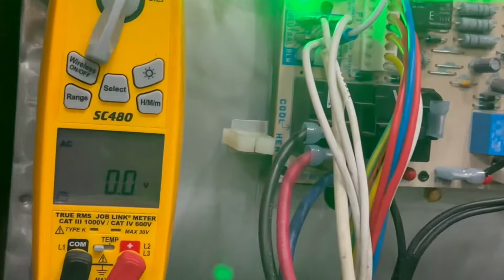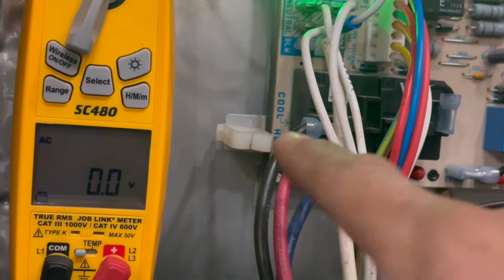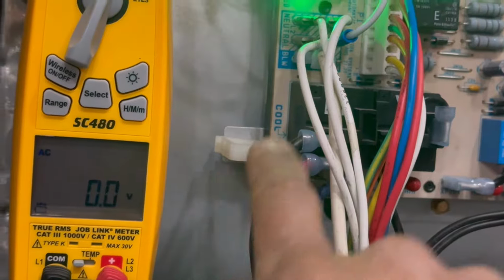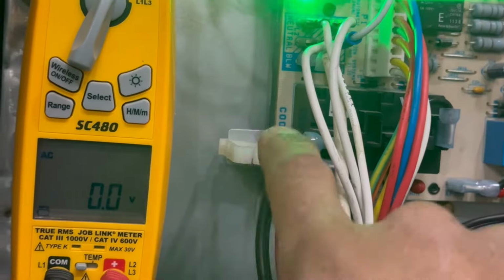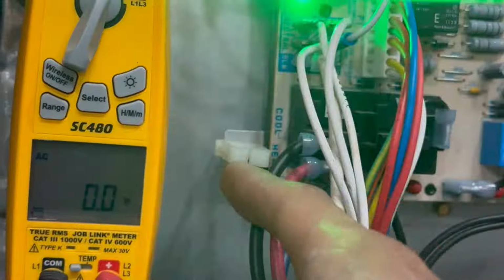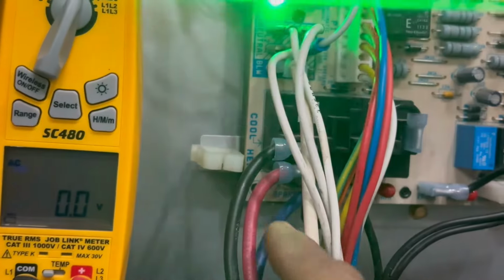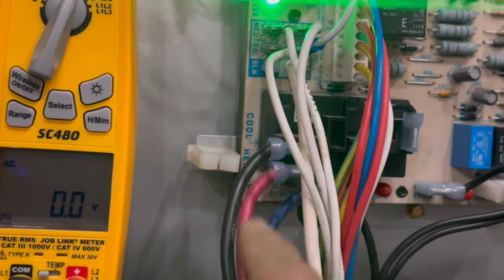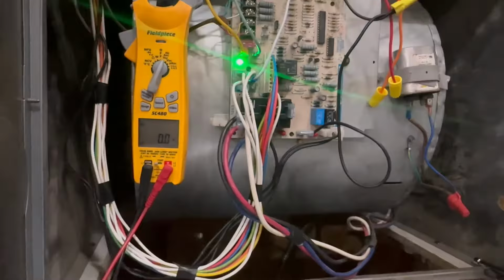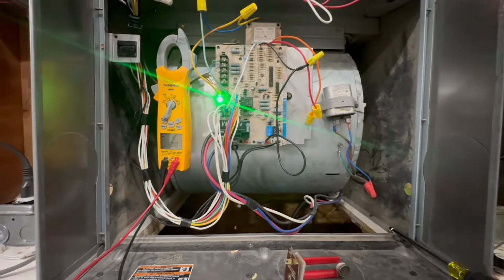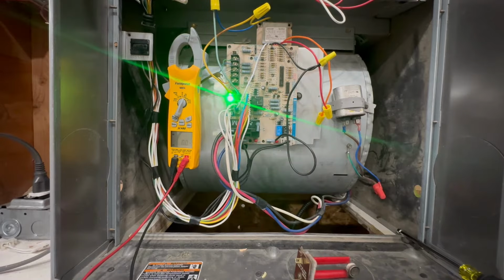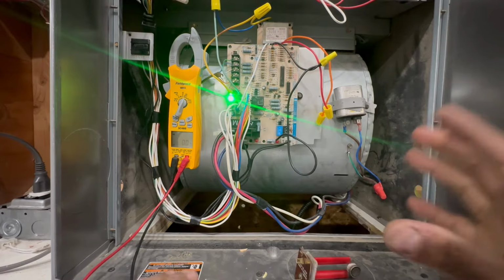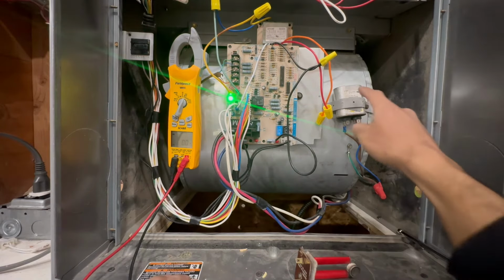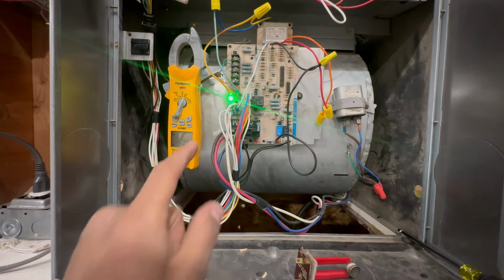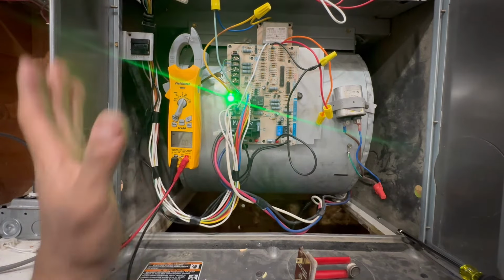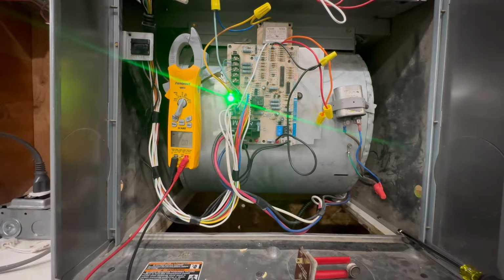But right here, it won't send 120 volts on this one. It's only going to send 120 volts on the cooling when you have a call for cooling. But when you have a call for heating on the W, it sends 120 volts through this one here. So now I have some airflow, and now you can supply hot air to the customer. But yes, you're checking if the motor is working well, the capacitor is good, you're ohming out the motor, and you're checking that the board is actually sending 120 volts to the motor to turn it on.